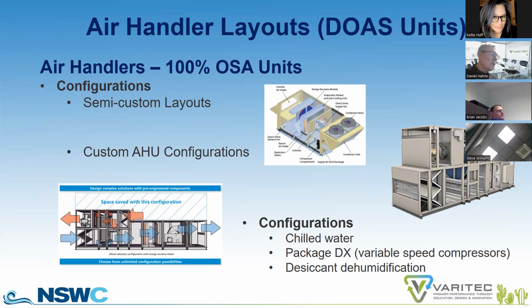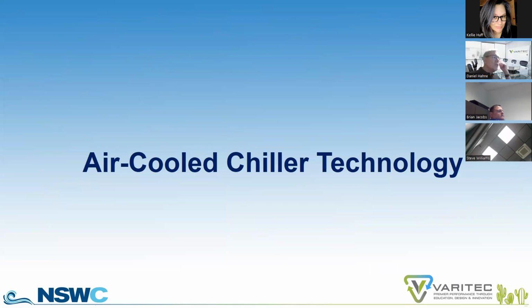And one of the best kept secrets in the industry is discrete use of desiccant dehumidification to maintain dew points at a proper level. It's a passive dehumidification solution that certainly is very attractive and gives you great control of your building humidity levels. So if you do use a DX solution for your DOAS, and you can decouple the DOAS unit from a chill water loop, so you only have one primary chill water loop serving a chill beam system, that chill water would be supplied at 55 degrees instead of 44 degrees.